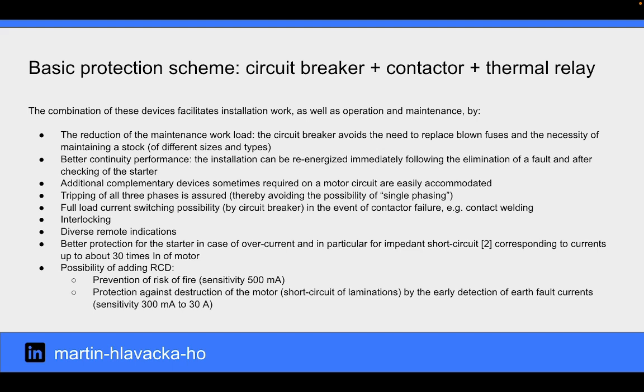The combination of circuit breaker, contactor, and thermal relay facilitates installation work as well as operation and maintenance by the reduction of the maintenance workload. The circuit breaker avoids the need to replace blown fuses and the necessity of maintaining a stock. Better continuity performance: the installation can be re-energized immediately following the elimination of a fault and after checking the starter.